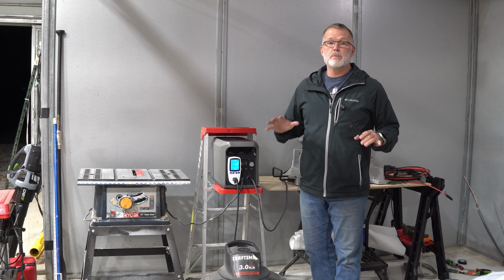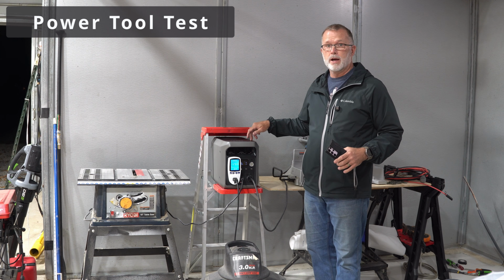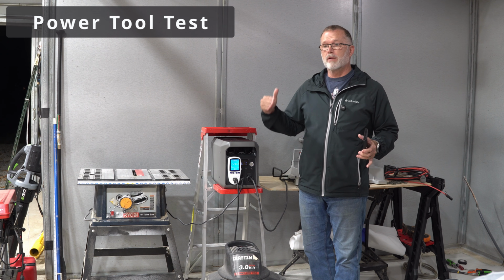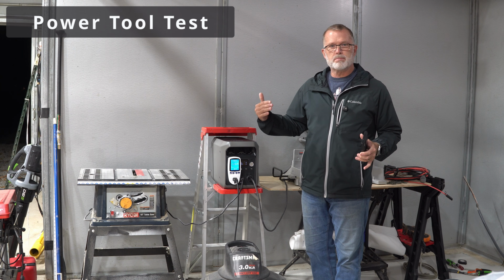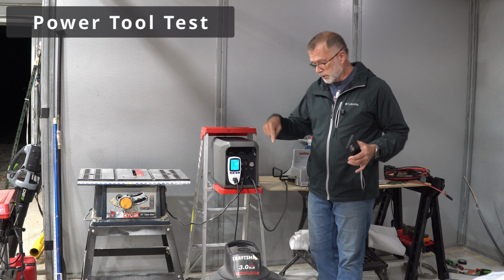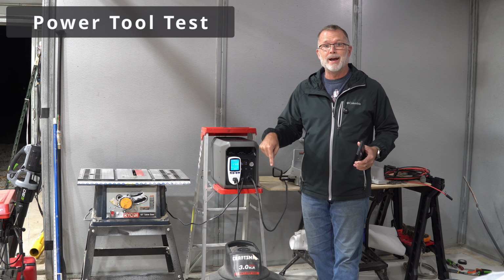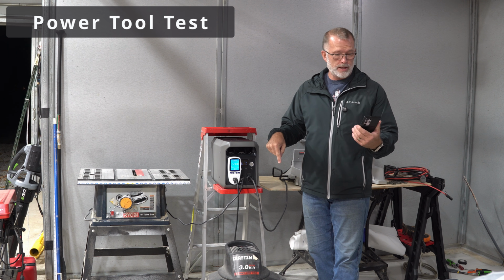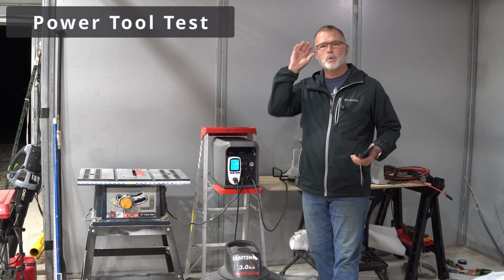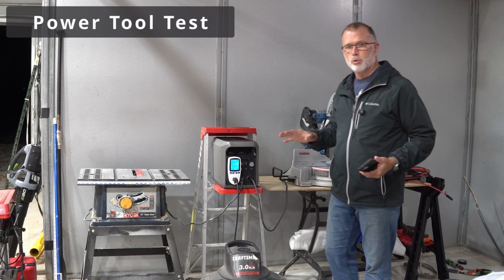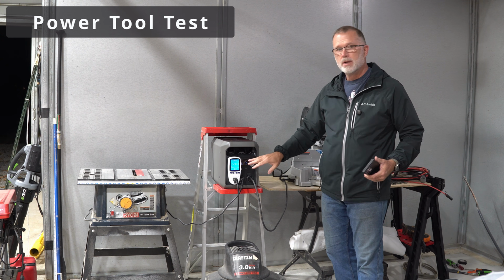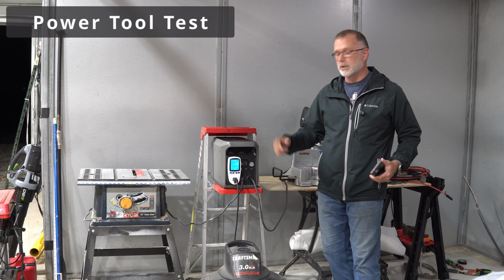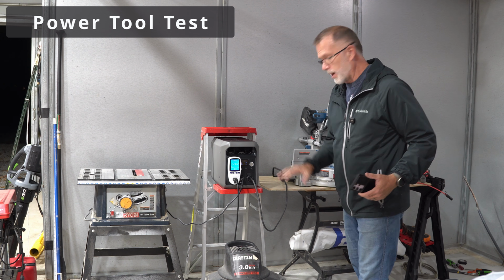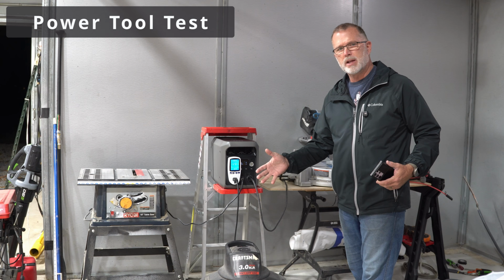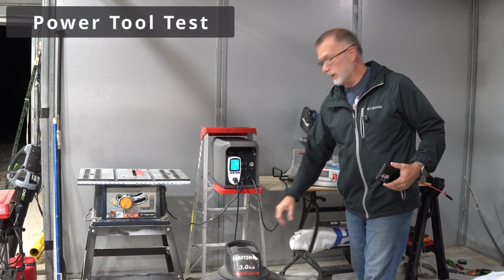Time to do the power tool test with this 2000NL. We're going to try 3 power tools covering a fairly broad spectrum of inrush current. First, a 3 horsepower, 8 gallon shop vac with an inrush current of about 27 amps. Let's see if it runs, and we'll watch the voltage to see if anything weird happens as we kick this thing on.